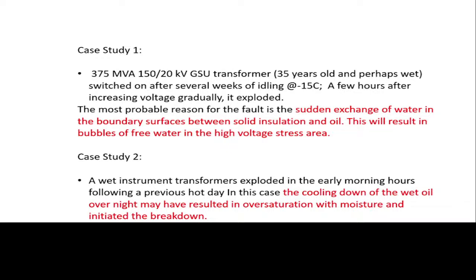Now here is a case study. I have given a couple of case studies. A 375 MVA, 150/20 kV GSU transformer, 35 years old, perhaps wet, is switched on after several weeks of idling at -15. That is, it is idling at -15, and suddenly it is switched on. A few hours after increasing the voltage gradually, it exploded. The most probable reason identified is a sudden exchange of water at the boundary surface between solid insulation and oil. So when there is a sudden exchange, you have moisture coming in from paper to the oil. This will result in bubble formation, especially if the paper is wet, and that will give rise to free water in the high voltage stress area, causing the failure.